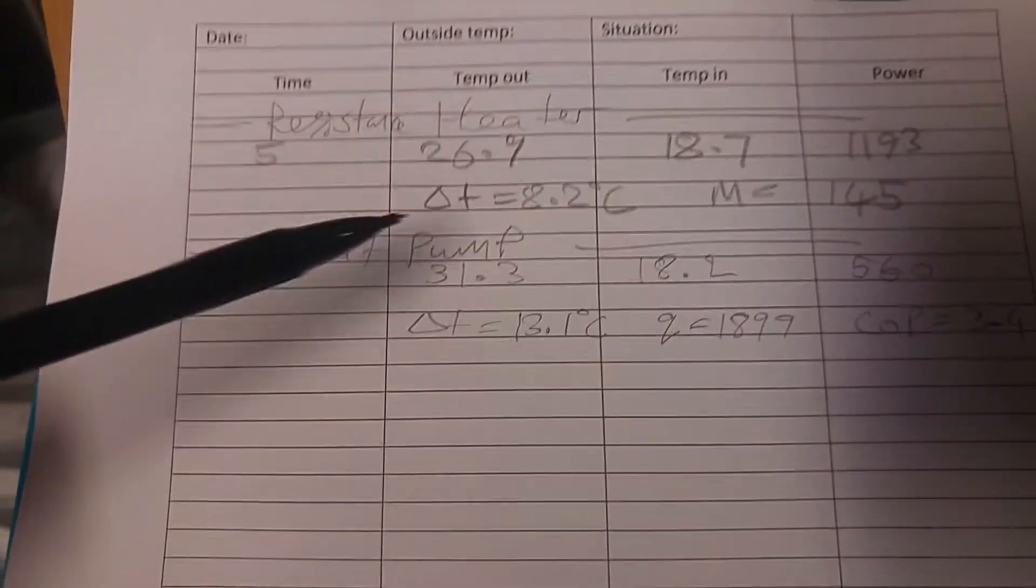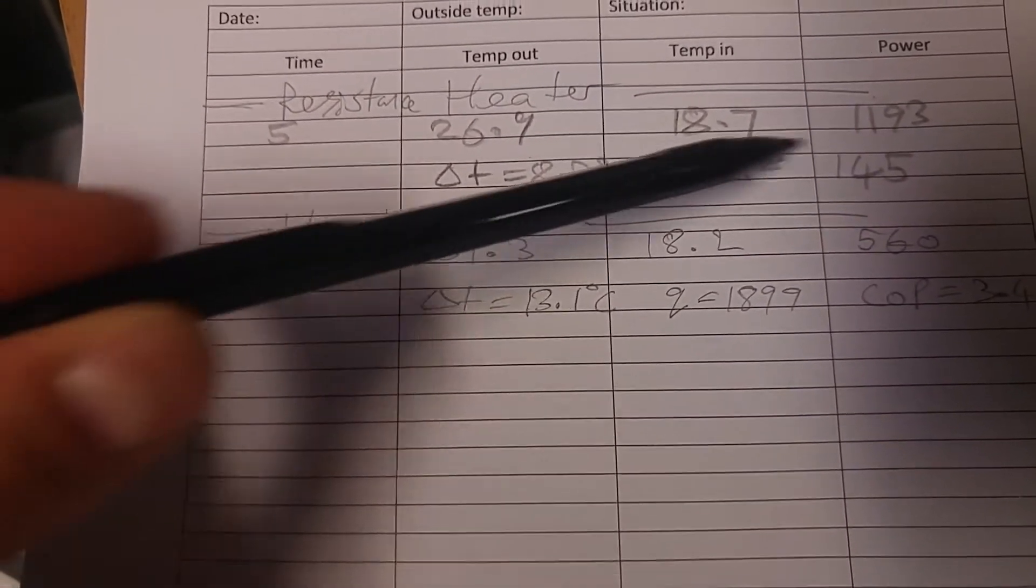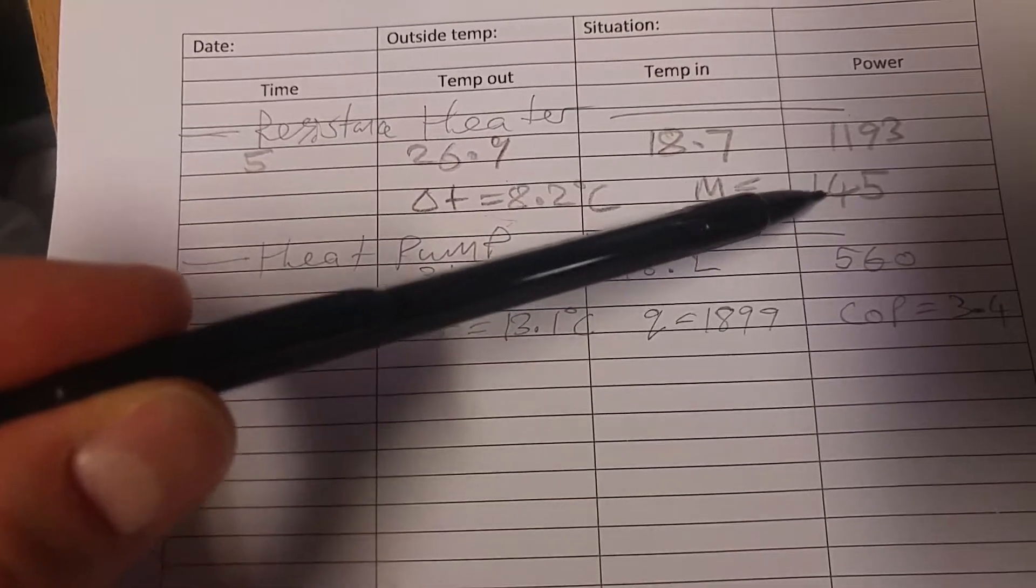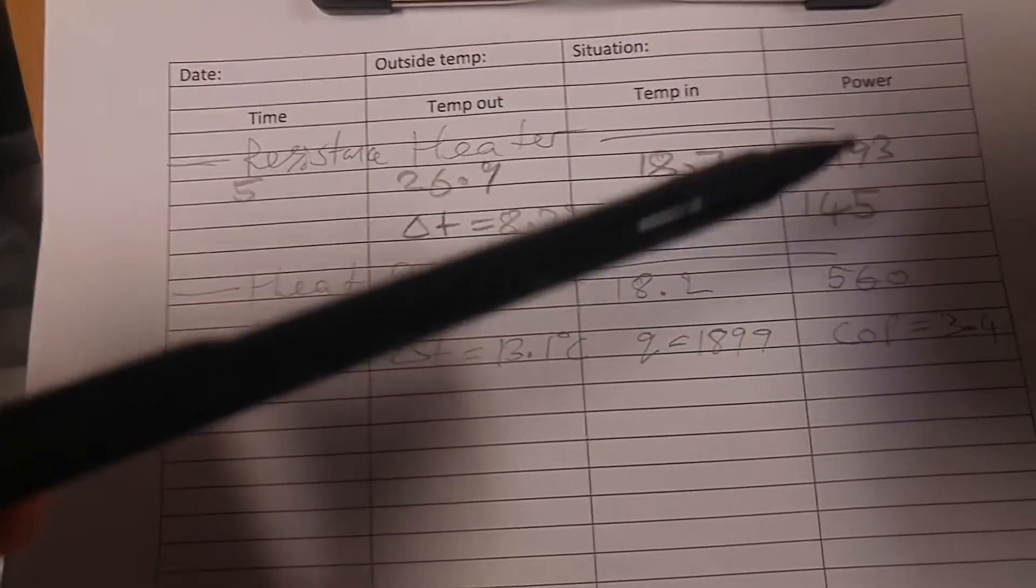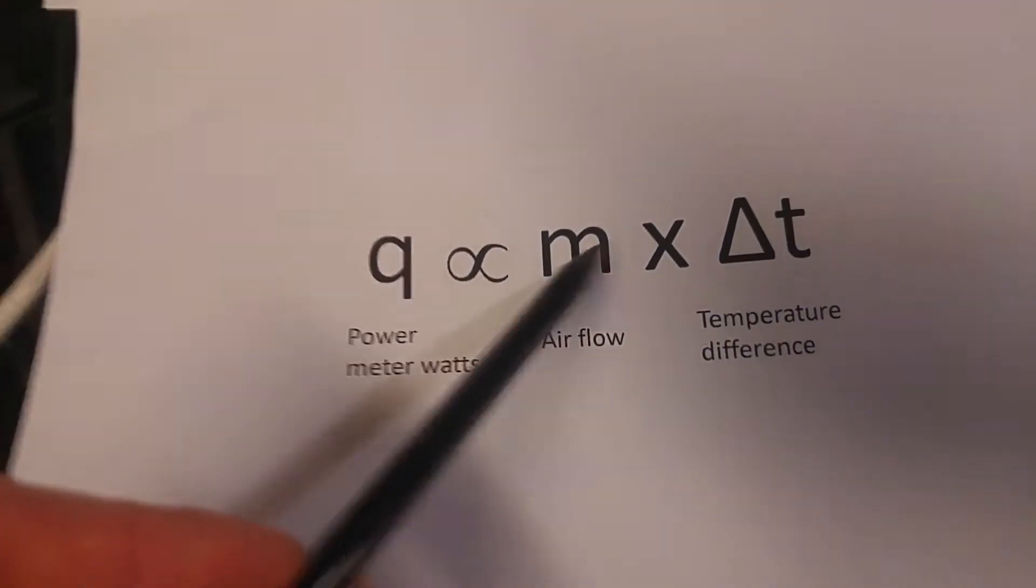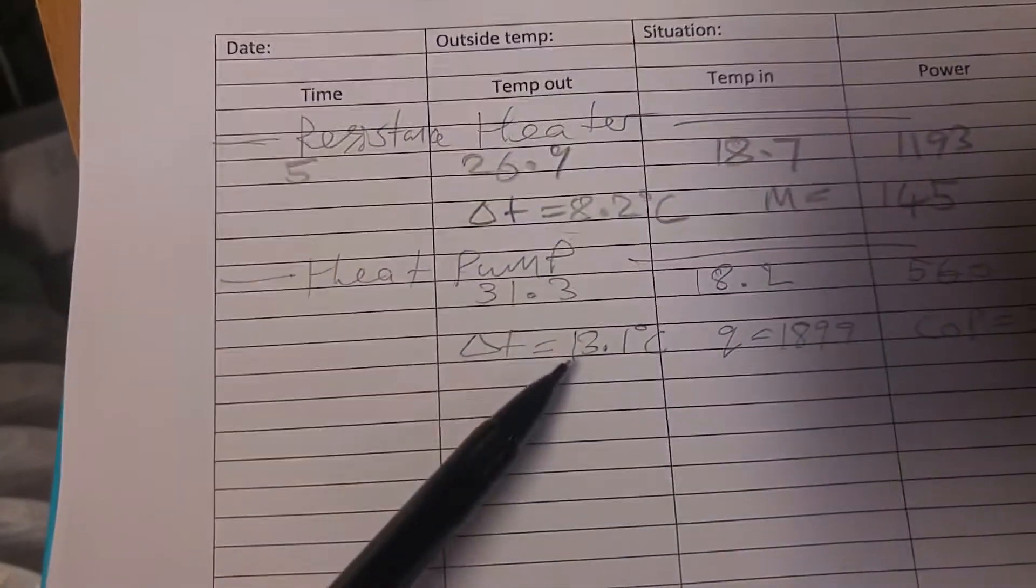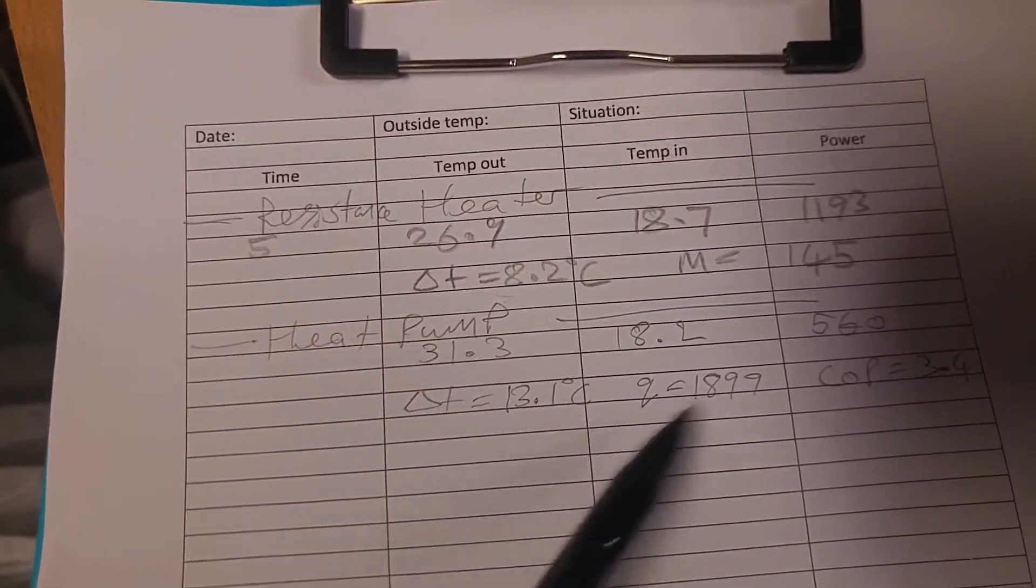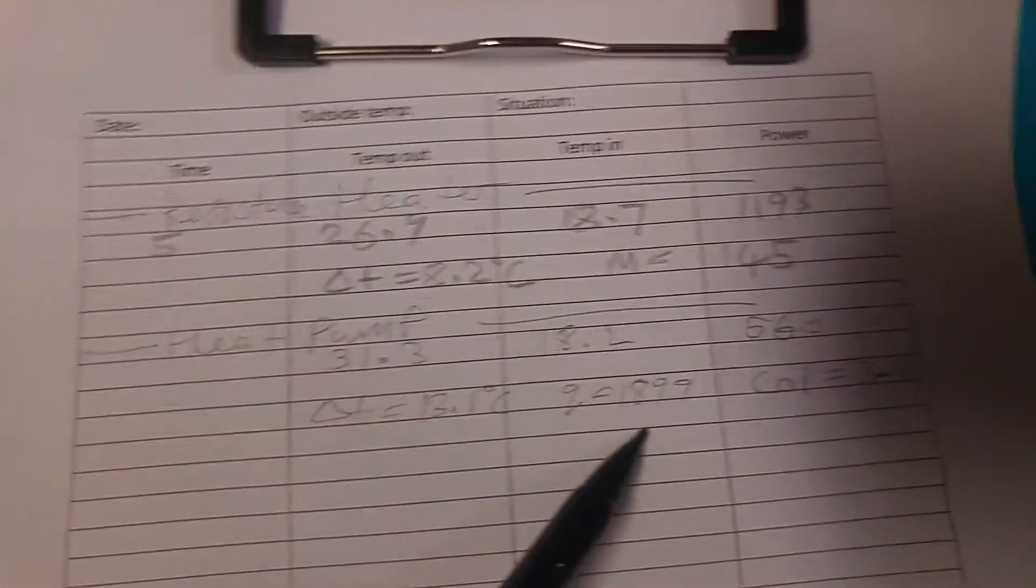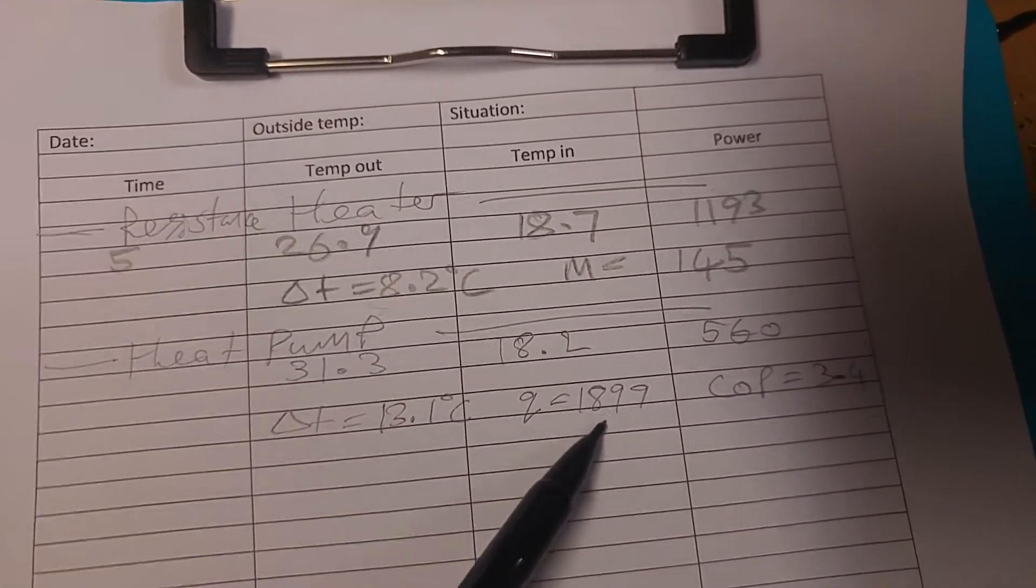Here are the numbers. That's the result for the heater, the resistance heater, where we've got the mass flow rate of 145. And then with the equation, let's plug that into there, times the heat pump delta T was 13. So that times that gives you that. And that is the power output of the heat pump.